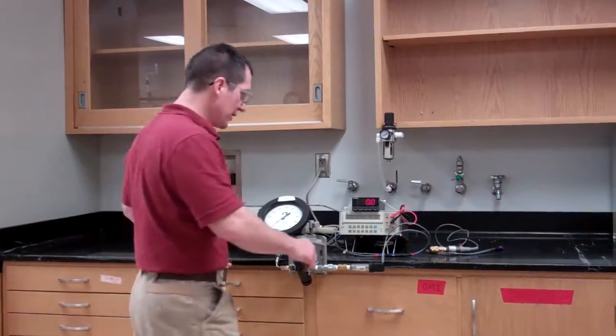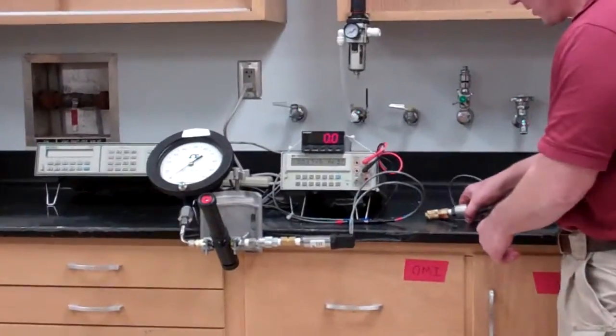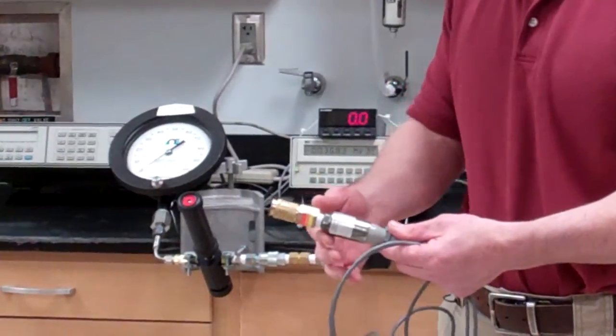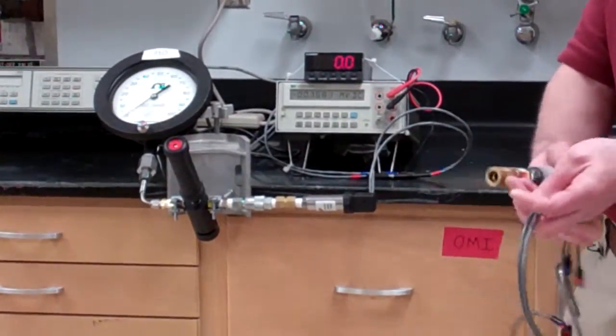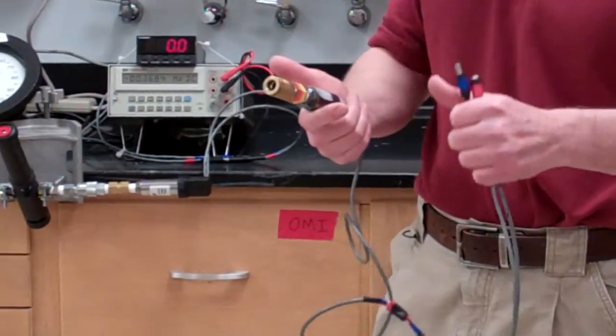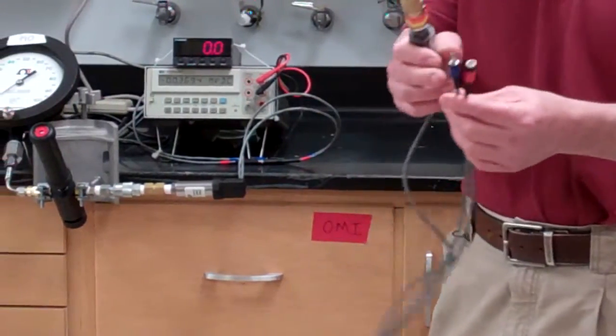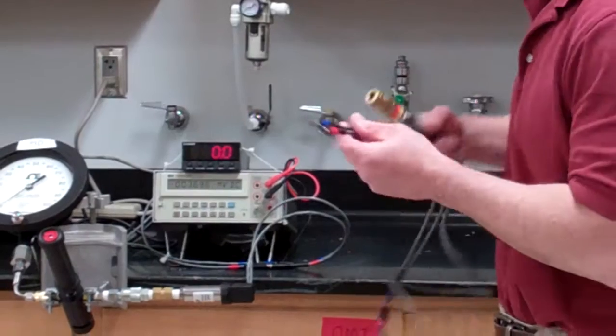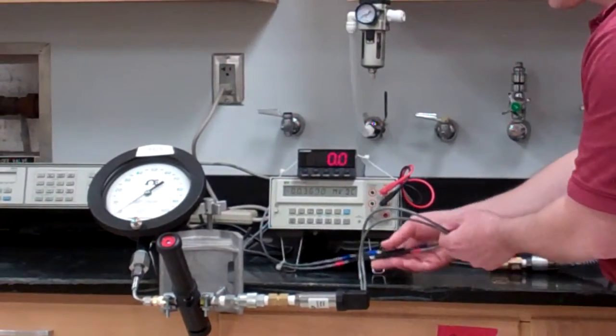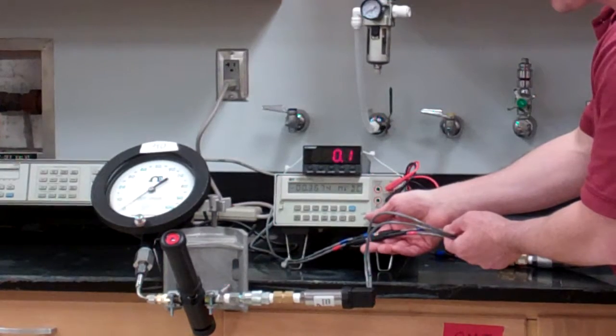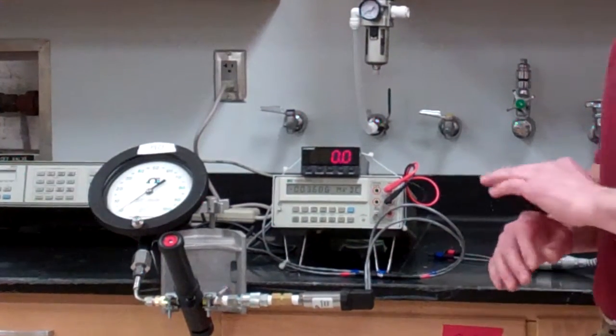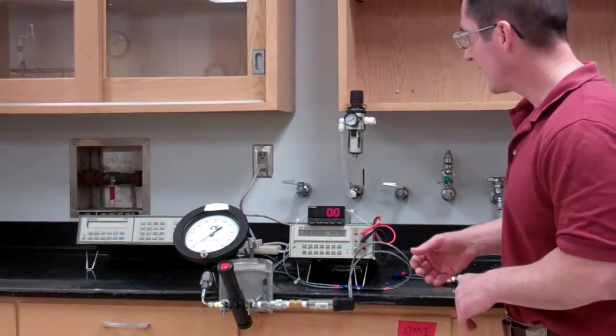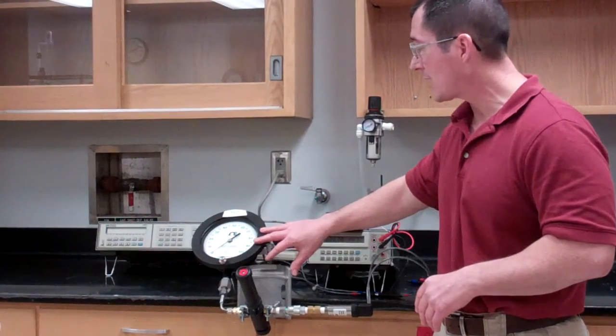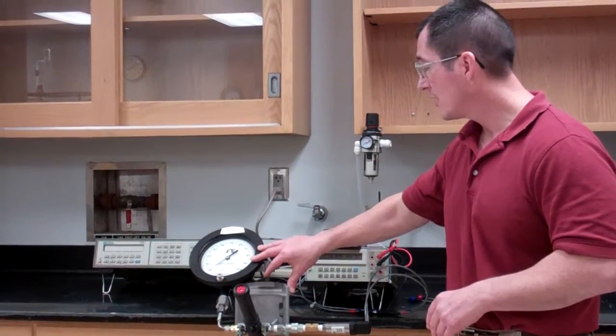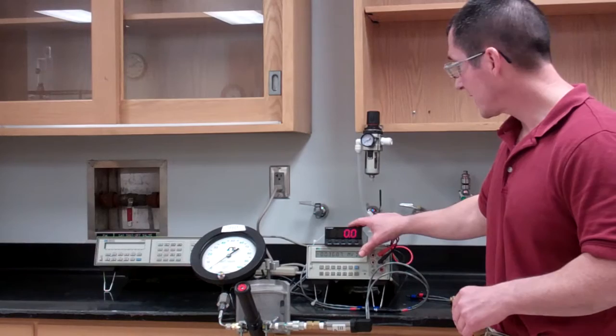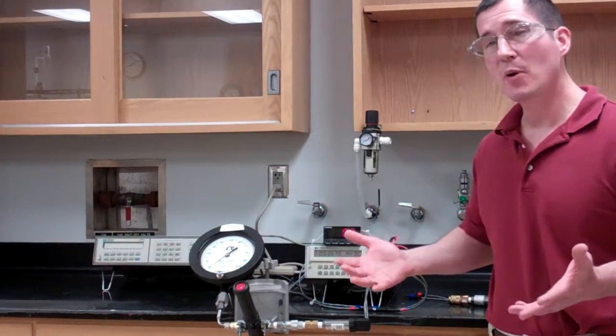So what we have is, this is the actual transducer here. There's another one here that you'll also calibrate. And so basically, there's two parts to it. It has an excitation power supply and an output signal. And that's what the blue and the red connectors are for. And as you can see, when you change from one to the other, you just have to unplug the connectors and plug in the new ones. And I have them set up so that you can't get them mixed up, so that's good. And this is a test gauge. This is a really accurate mechanical Bourdon gauge that is used for calibrating pressure transducers. And so why is this part so important?